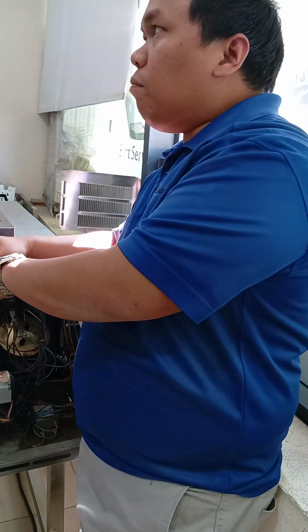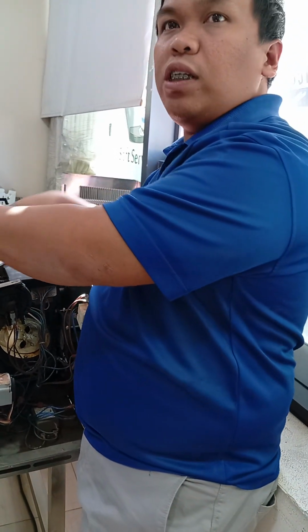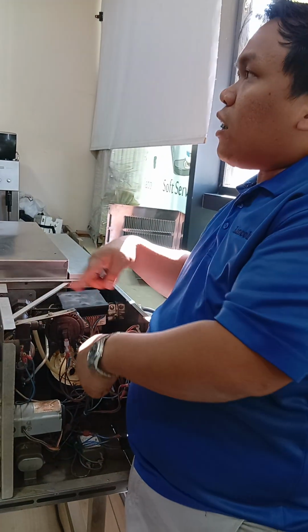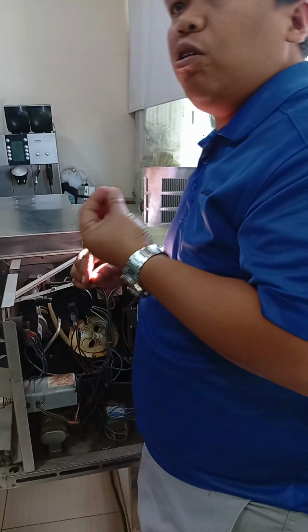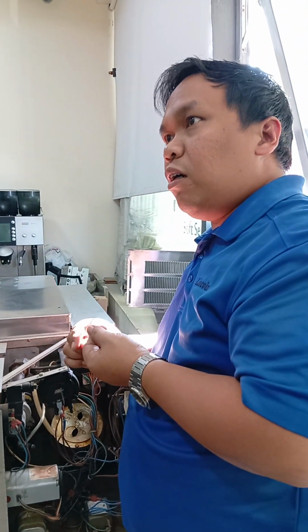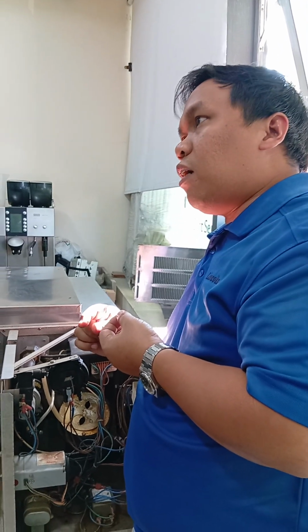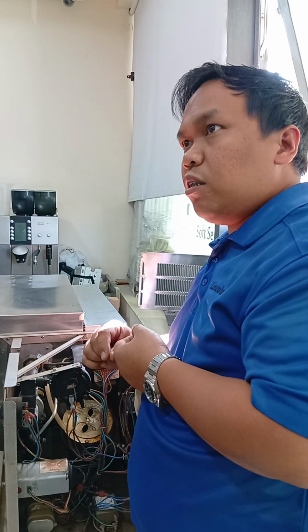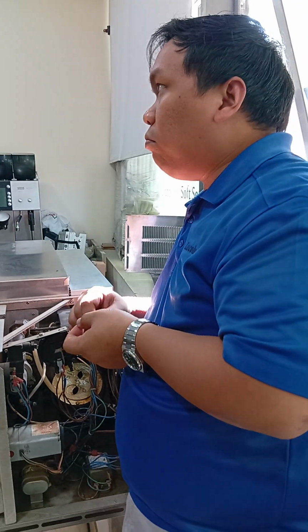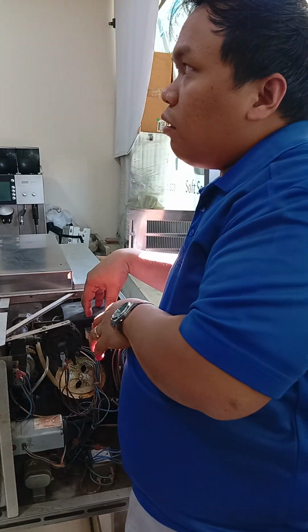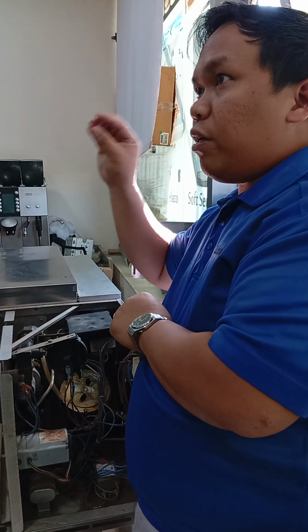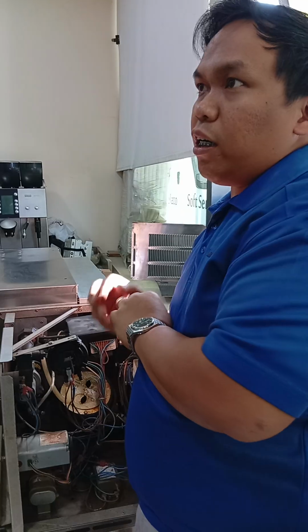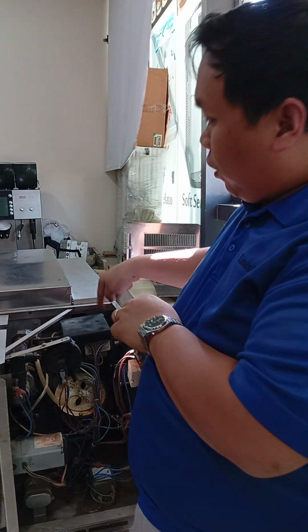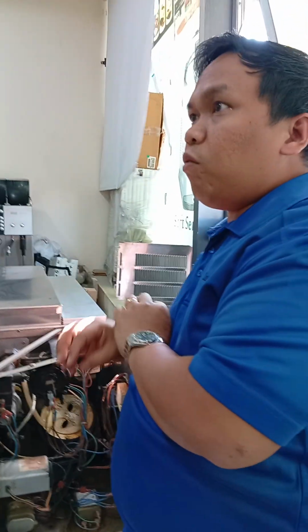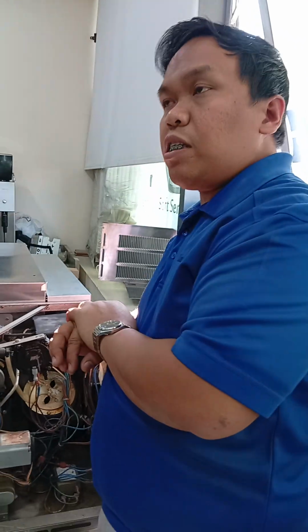For preventive maintenance, important is the cooling system. Okay? Wiring needs to be inspected. If there is some discoloration, or weak cables, loose connection, you need to inform. For the heating element, you need to make sure there is no burn mark. So the heating element, you can see visually on the side some of the connectors of the wire. That is if it is electric. If it is gas, you need to inspect the blower. Okay.